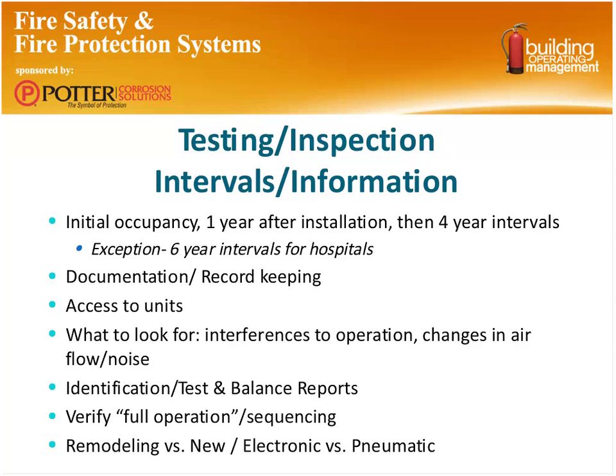We even have a few authorities in our area now that are requiring that on an annual basis, when the visual inspections are done, those dampers have a photograph taken, and this is more so in the hospital environment, and that they vacuum off all the blades and make sure the dust and lint are off of them. And if you think about it, it could be an important factor. If you have a smoke or fire damper that isn't clean, there's a good chance that you're going to get some leakage during a fire event. So could be important.